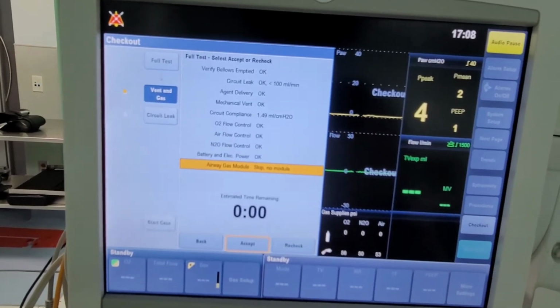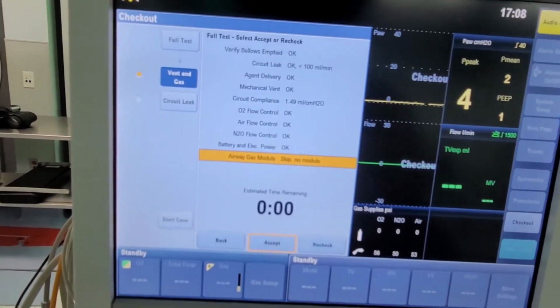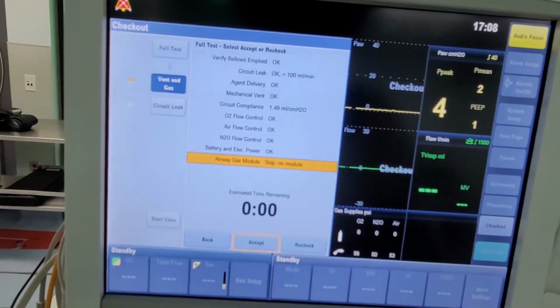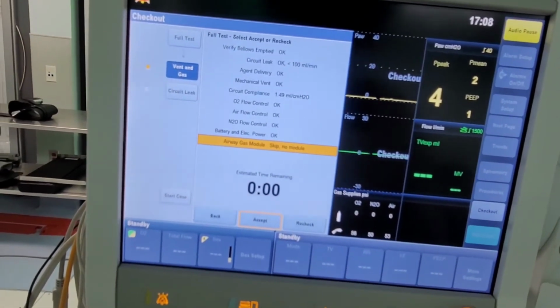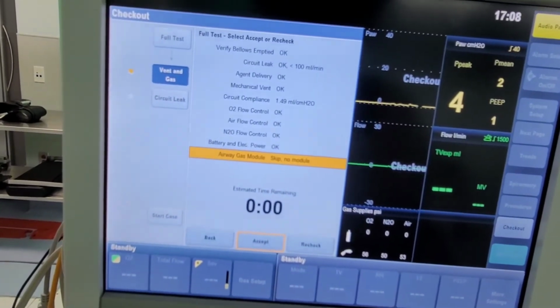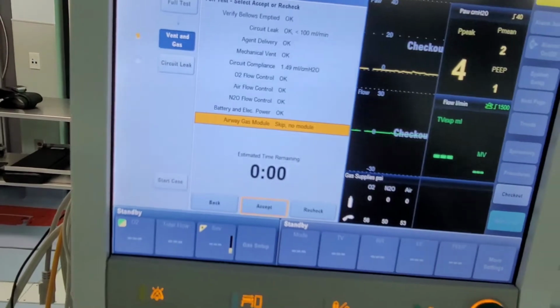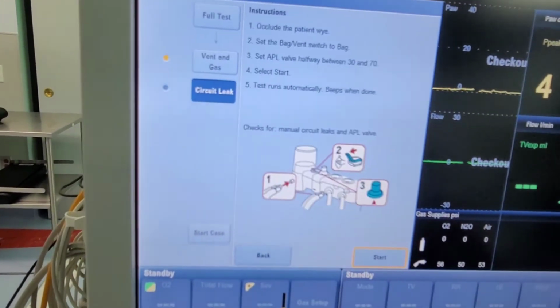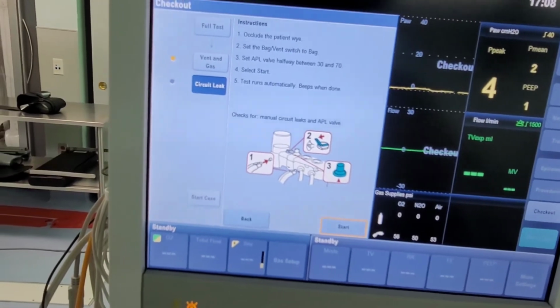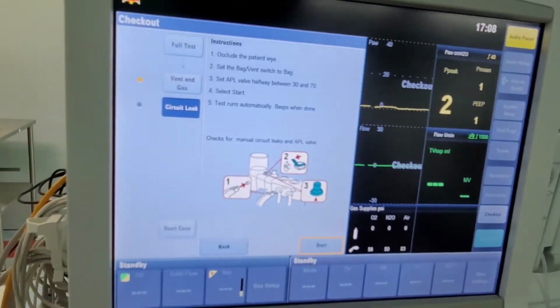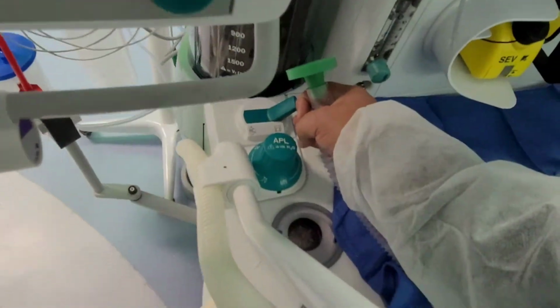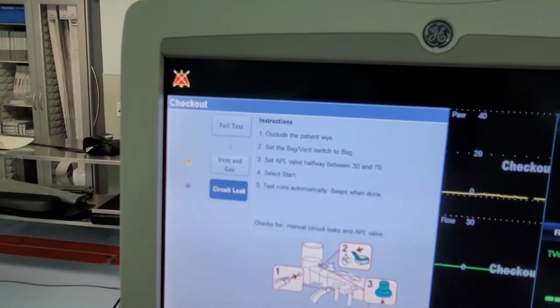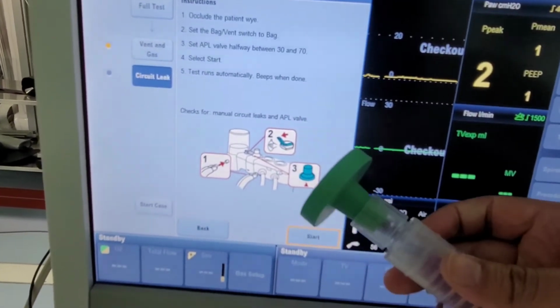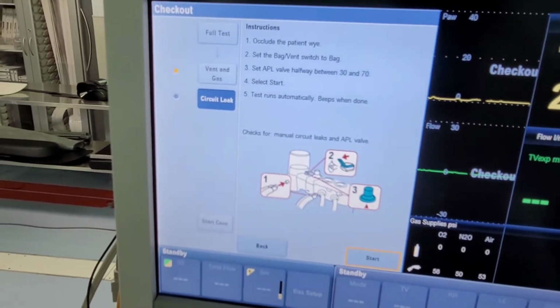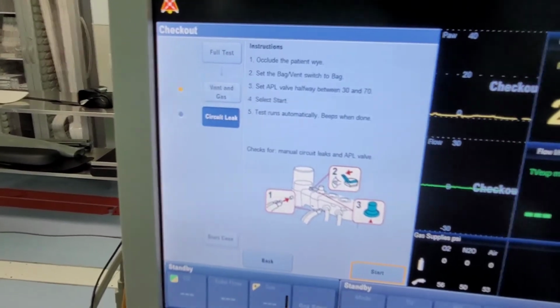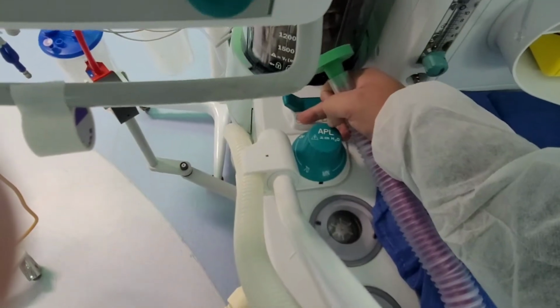The agent delivery, which is from the vaporizers, mechanical ventilation through the bellows, and circuit compliance, same thing. It does any kind of measurement of leaks. O2 flow control, air flow, N2O, battery, it's good. So we'll accept. Now we're at the point of testing the manual or bag mode. Instructions show here to occlude the bag Y, which is already done. Set the bag vent switch to bag, which we did. Now it is on bag.